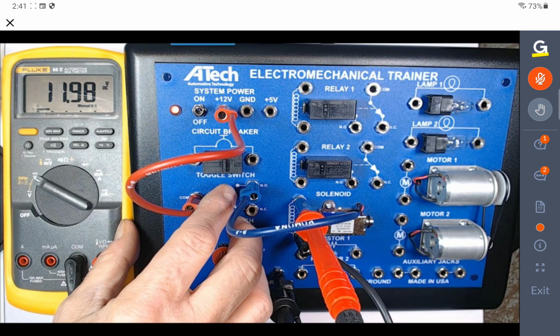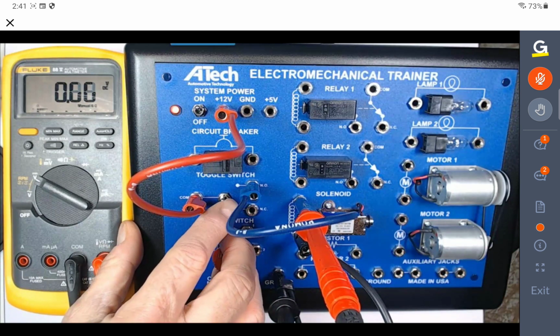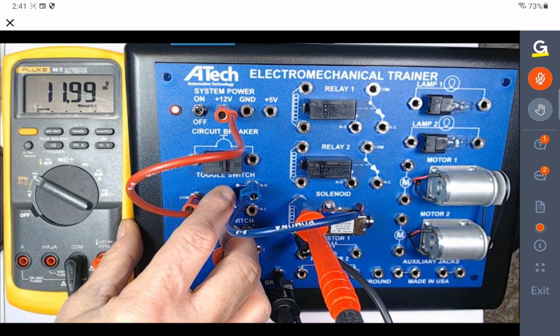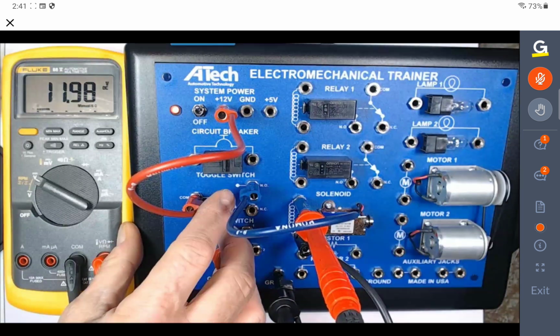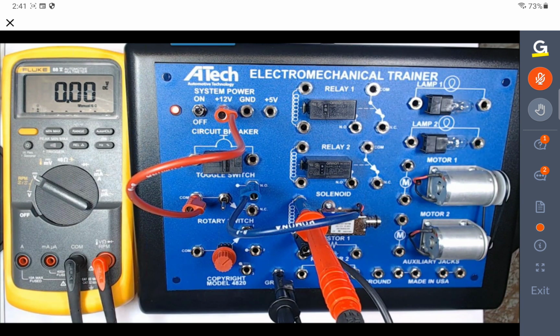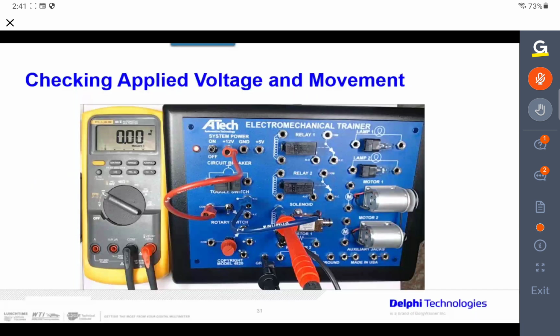You can't hear it, but there's a nice little click when that thing goes on and off. I want to make sure I have applied voltage to it, which is battery voltage, and that I see movement. Why is this important? Because sometimes there's a loss in voltage to a particular circuit. On this circuit, I might have a loss, so I need to know if I have adequate voltage being delivered to the solenoid—say I had only 10 volts, it might not work, or not work properly. So make sure you have the proper applied voltage and amperage, and you can check both with your meter.